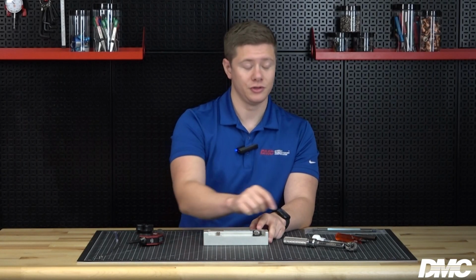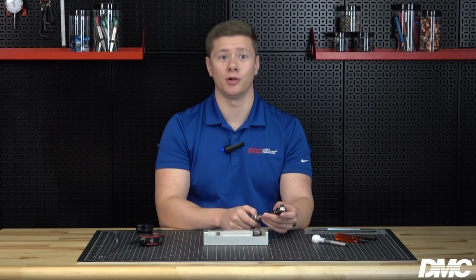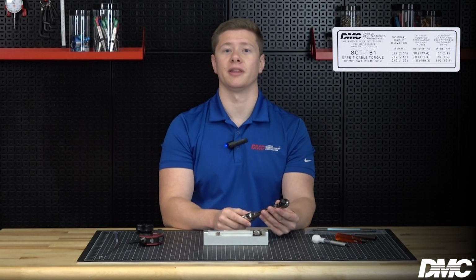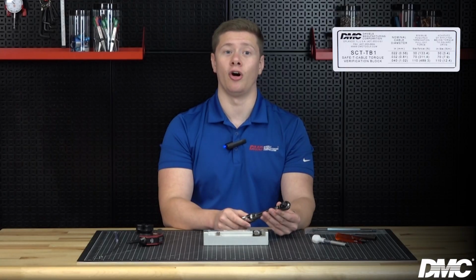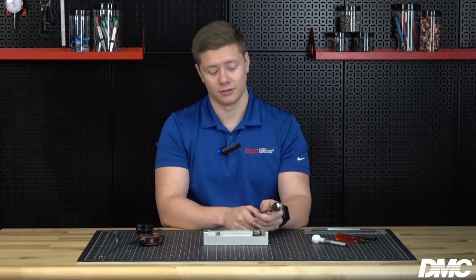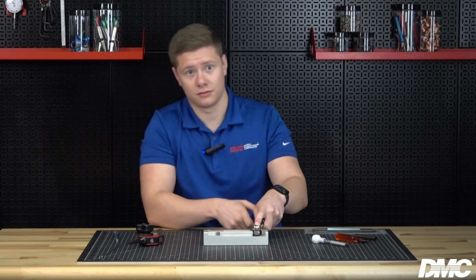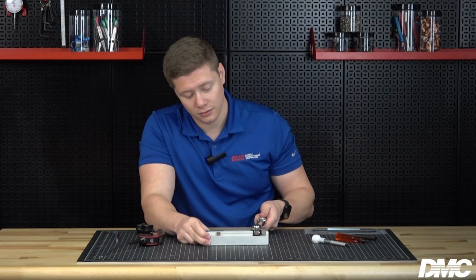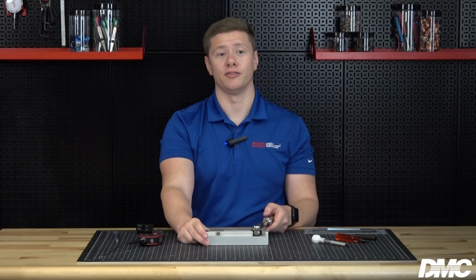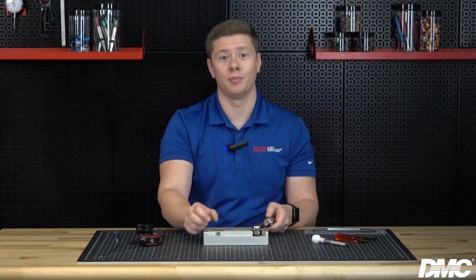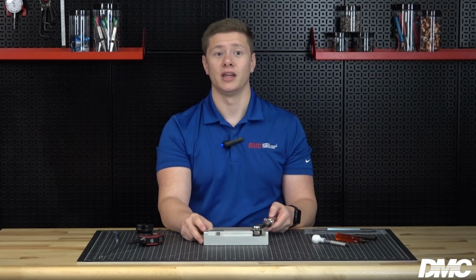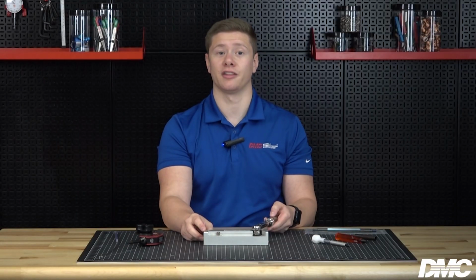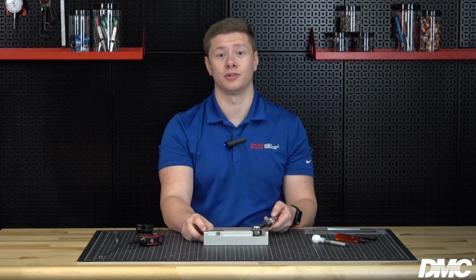Install safety cable on the torque verification block. Use a calibrated torque wrench to apply the proper pull-off load. The pull-off load is determined by the cable diameter and is indicated on the verification block. Release the torque when the minimum pull-off load is achieved. Do not apply additional tension to the cable. If the cable breaks off or pulls out of the ferrule, the crimp is unacceptable and the tool should be adjusted.